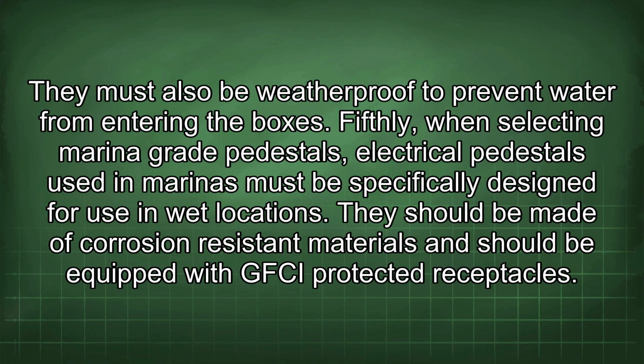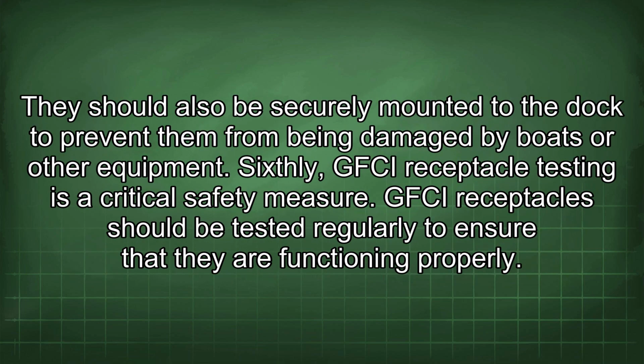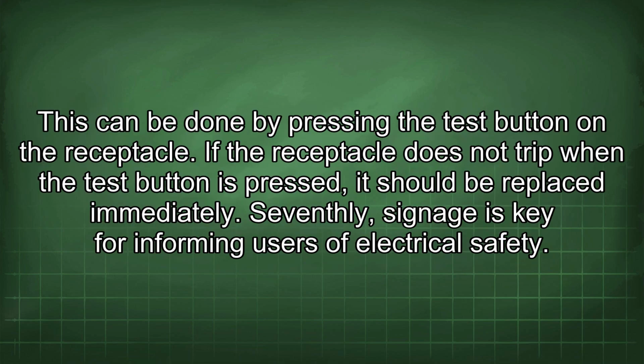Fifthly, when selecting marina-grade pedestals, electrical pedestals used in marinas must be specifically designed for use in wet locations. They should be made of corrosion-resistant materials and should be equipped with GFCI-protected receptacles. They should also be securely mounted to the dock to prevent them from being damaged by boats or other equipment. Sixthly, GFCI receptacle testing is a critical safety measure. GFCI receptacles should be tested regularly to ensure that they are functioning properly. This can be done by pressing the test button on the receptacle. If the receptacle does not trip when the test button is pressed, it should be replaced immediately.